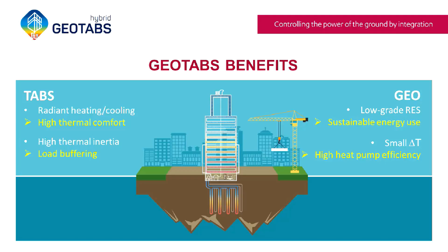However, there are, of course, a number of challenges, otherwise we would not be here today. On the side of TABS, the high thermal inertia of a TABS floor makes it difficult to reach comfort in moments where there is a very sudden increase in heating or cooling demand, because, for example, the sun hits the building or many people come into a room, which might suddenly increase heating or cooling demand, and this cannot always be directly covered by the TABS. A second aspect can also be with regard to acoustics or dehumidification.